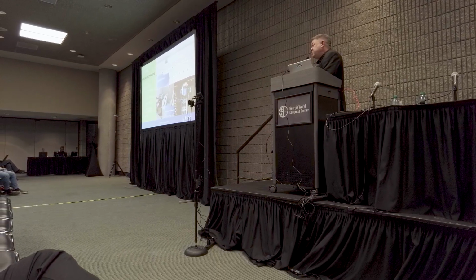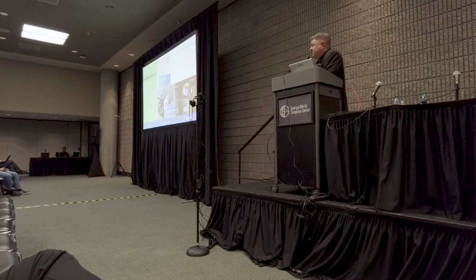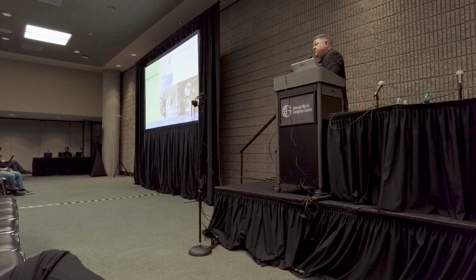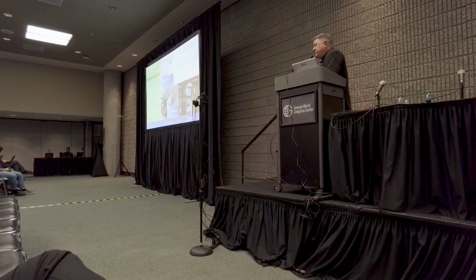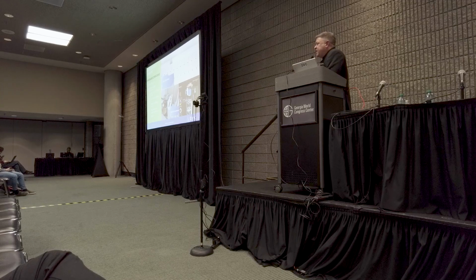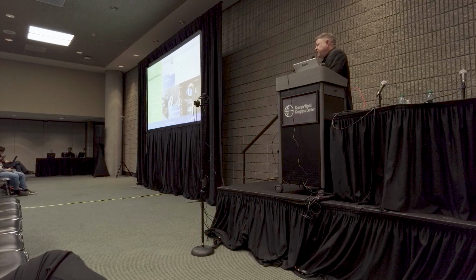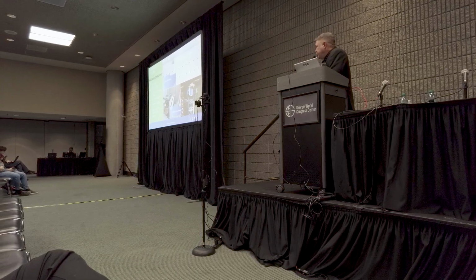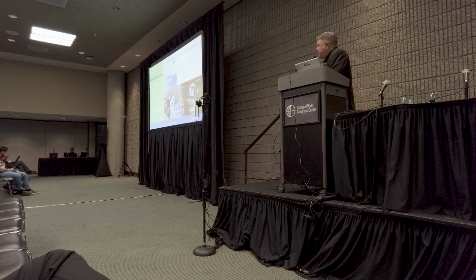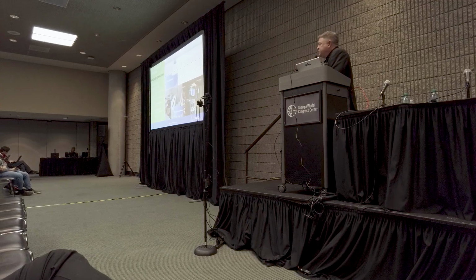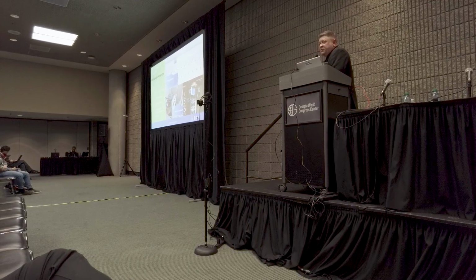The fans in these systems produce up to 10,000 CFM at the supply side, and a redundant fan in the rear brings 10,000 CFM off the backside, eliminating hot spots in the back of the cabinet and producing a tremendous amount of precision-controlled air so you can keep the operating environment inside these cabinets ideal so your server hardware works as good as it possibly can.